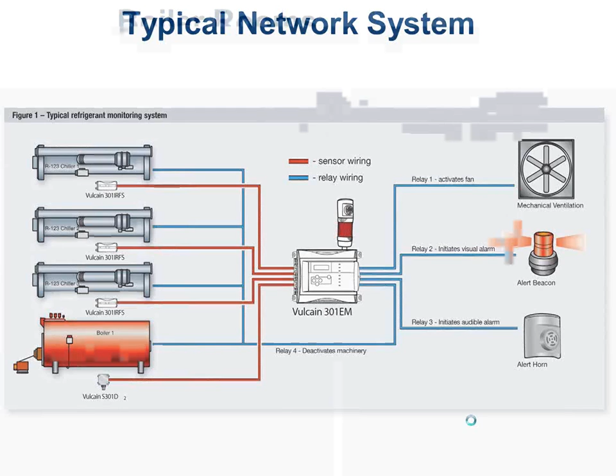In a boiler room, the things that I'm most likely to monitor, carbon monoxide is the most common. We already mentioned the thresholds for that, so I might want to measure that in my boiler room. And then I may also be concerned with measuring methane in there, depending on what my boiler is doing. So I may measure that. But in general, carbon monoxide, which you'll see in most boiler rooms. Methane is typically lighter than air, so it's going to rise up to the ceiling, so I want to measure that one at the ceiling. Carbon monoxide is approximately the same weight as air, so I'll measure that at the breathing zone limit, 5 feet above the floor approximately.